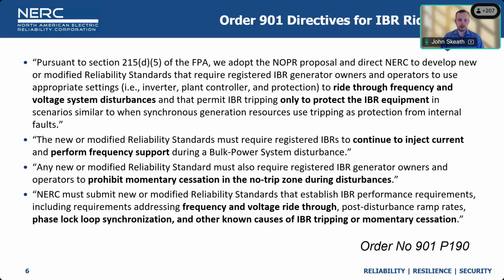Additionally, the order required that the IBRs continue to inject current and perform frequency support during the bulk power system disturbance, that is, riding through the disturbance rather than separating out from the rest of the bulk power system. Further, they've said there needs to be a prohibition of momentary cessation in the no trip zone during disturbances, and you can kind of see that calls into some of the IEEE 2800 language of certain zones of operation and expectations during those zones.